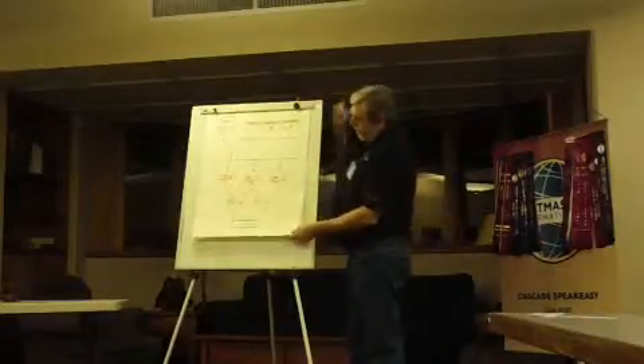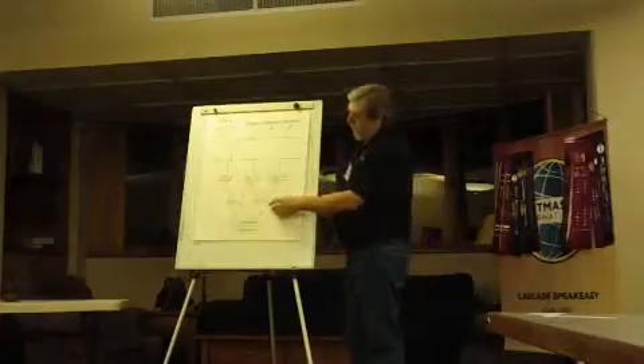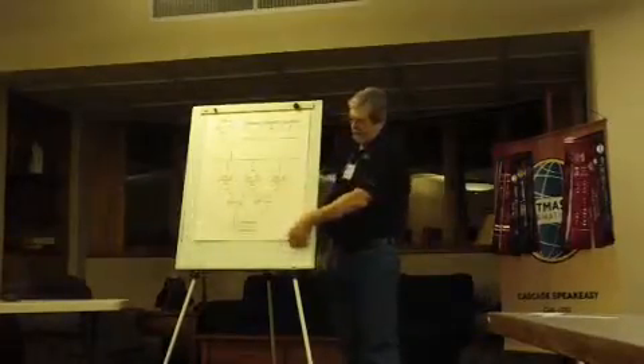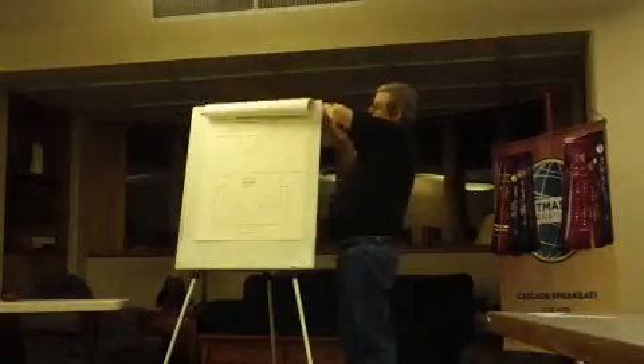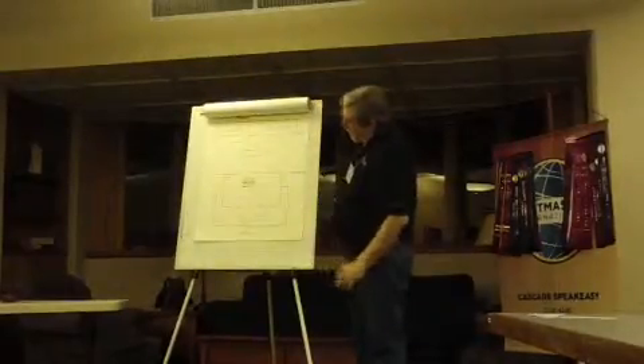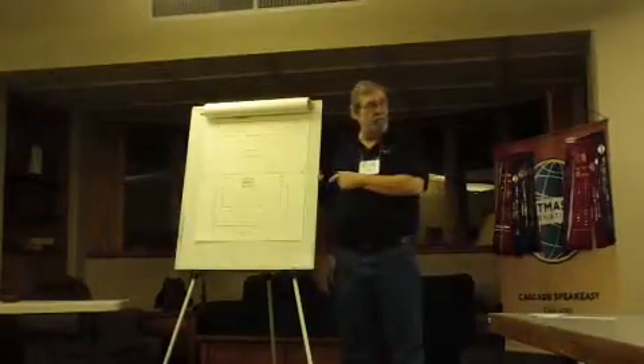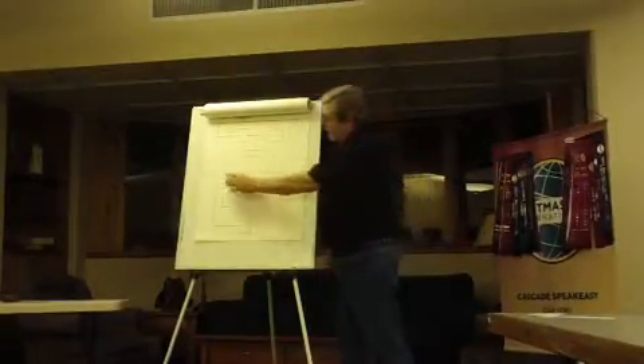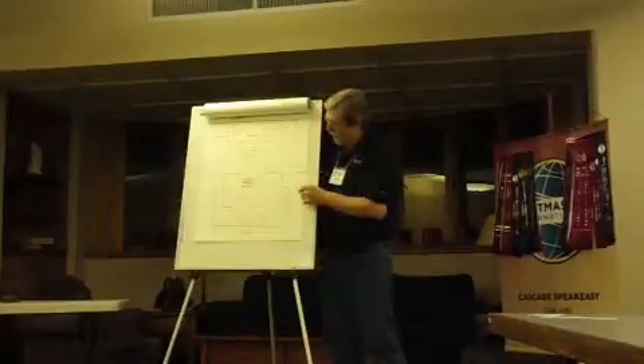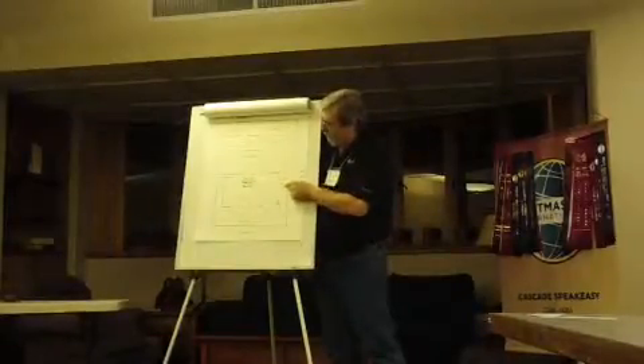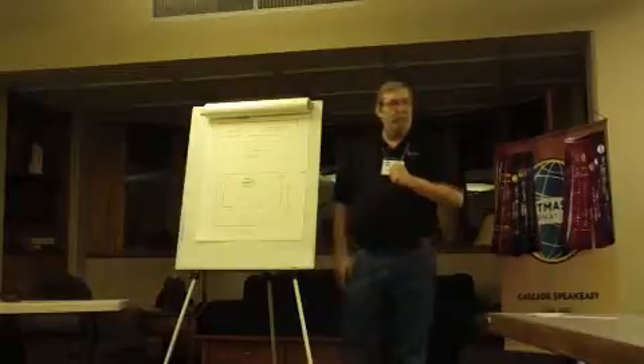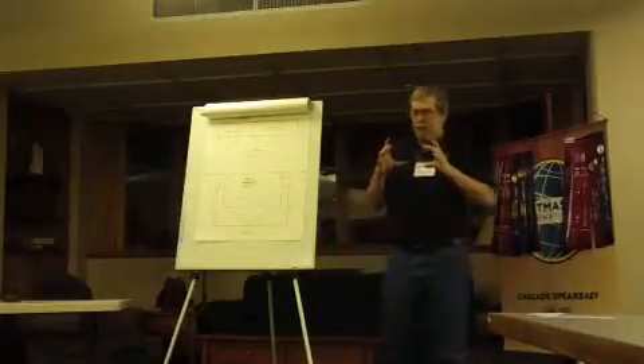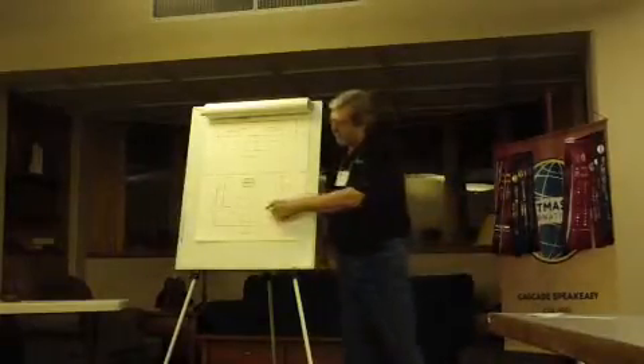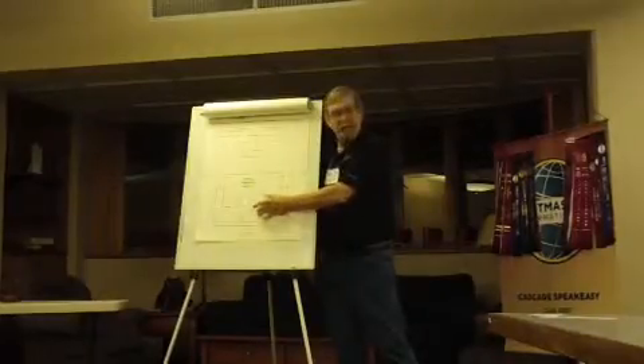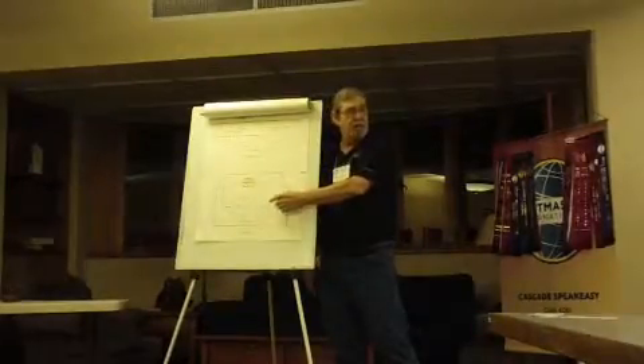The next part of it I wanted to talk about is a static transfer switch. And I've got a diagram of this that I drew. So a static transfer switch actually has two sources of power to it. It has a source 1 side, which is normally the primary side, and a source 2 side. A static transfer switch has two things called SCRs, or silicon controlled rectifiers. Basically, it's a fancy name for a really fast switch.